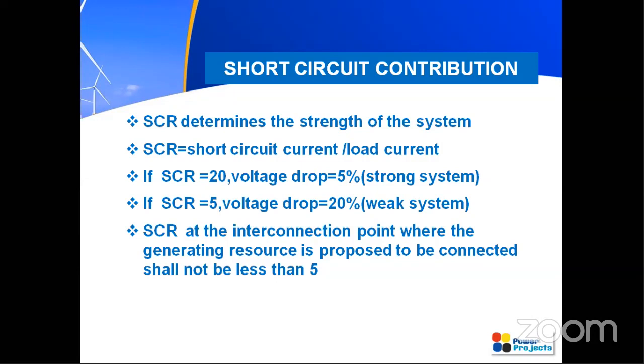First, the short circuit ratio is the ratio of your short circuit current and the load current. Take for example a system with a short circuit current of 20 kiloamps. If the load current is 1 kiloamp, the short circuit ratio will be 20 by 1. Just for simplicity, I'm taking the load current as 1 kiloamp. So it is 20 kiloamps by 1 kiloamp, which is 20. If your short circuit ratio is 20, the voltage drop is nothing but 1 by the short circuit ratio. If you take the reciprocal of this, you will get 5%. So this is a strong system.